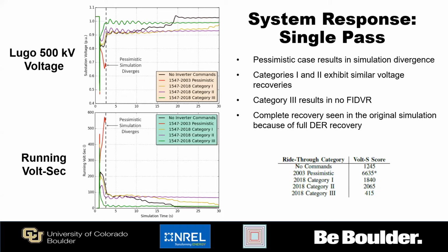Here you can just see some of the voltage profiles at different locations. At the top here, you see the voltage profile at that location where we have the fault. In this case, after about 2.5 seconds, the 2003 pessimistic case simulation diverges. This doesn't necessarily mean the system went unstable, but it's obviously not a good sign either. Then you can see how the voltage recovers for those other cases. The voltage is still at a pretty low level, recovering at just over 0.9 for the category 1 and 2 cases, whereas for the category 3 cases, we're recovering much closer to 1 per unit.